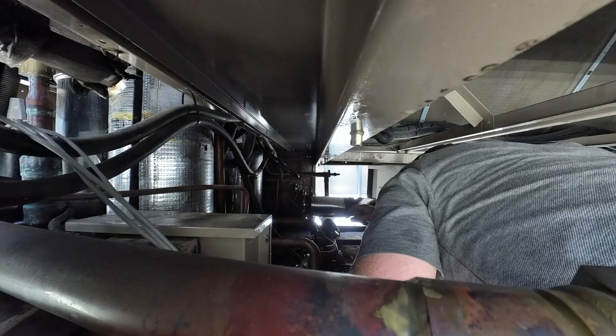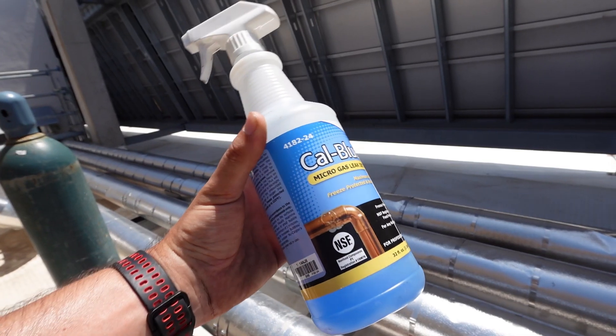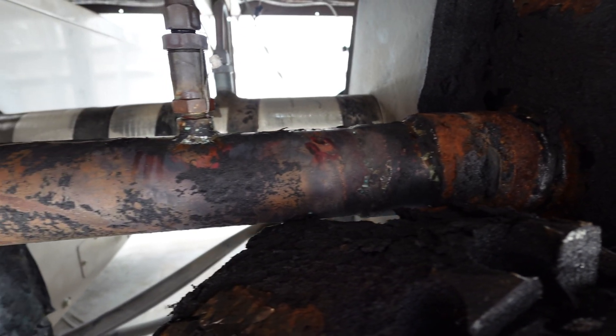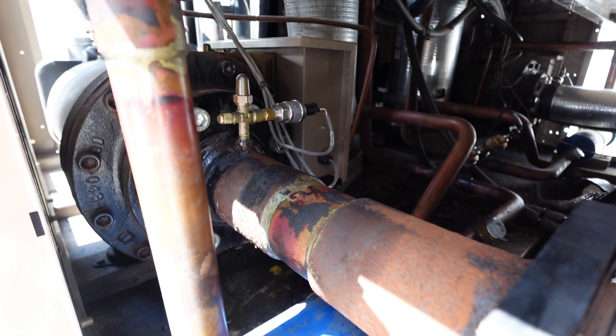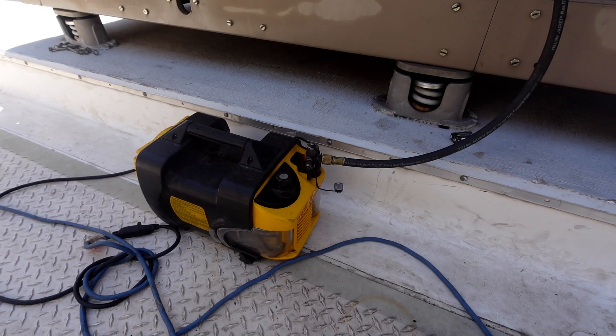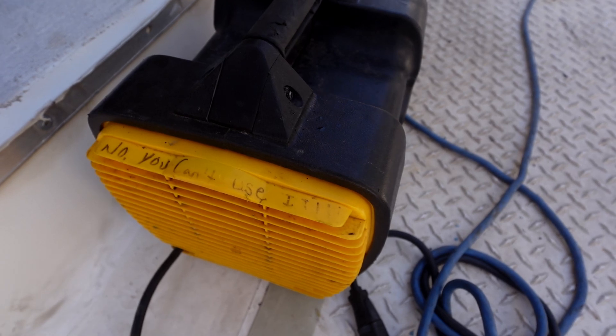We've spent three days trying to search this whole machine. We tore everything apart, went through the entire system, and can't find anything anywhere. To make matters worse, we held pressure on the system with nitrogen for two days at 100 psi with no issue. Our next steps are to pull a vacuum on this circuit, recharge it, get enough refrigerant in there to let it stay online, then let it run, let heat build up in the high side, get some head pressure in there, shut the circuit down with the high side hot, and re-leak search. I'm quite confident that's when we'll see our leak.